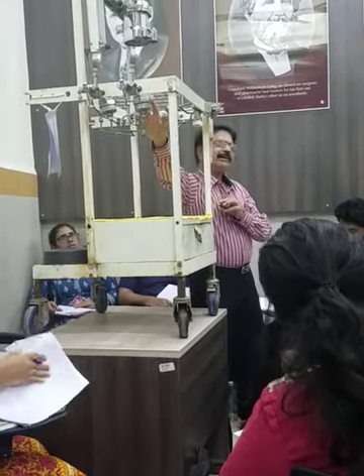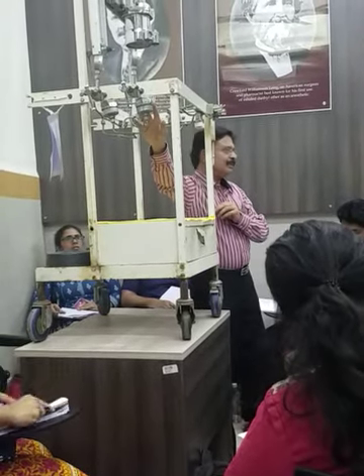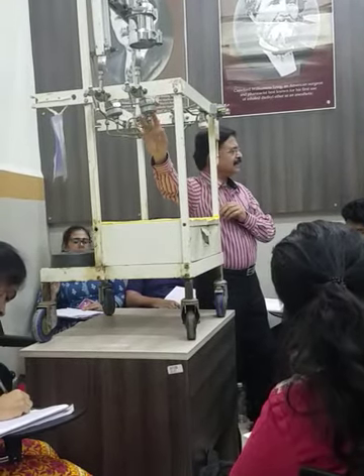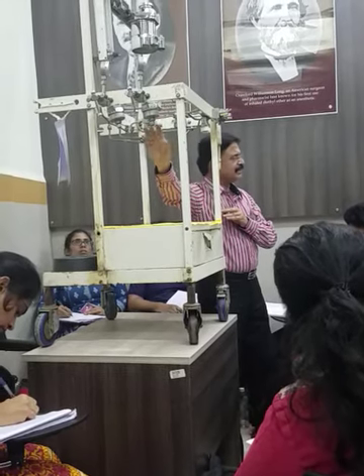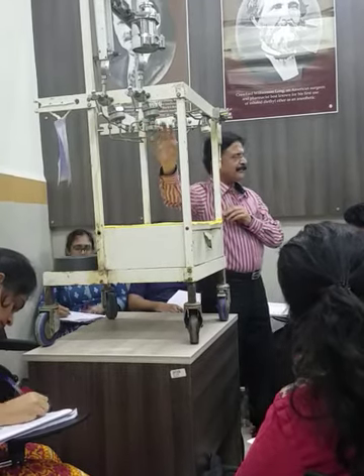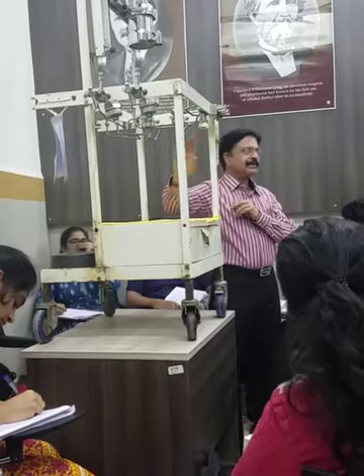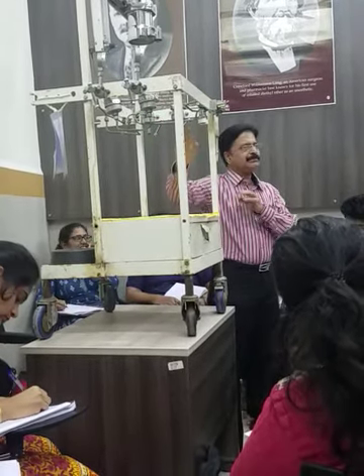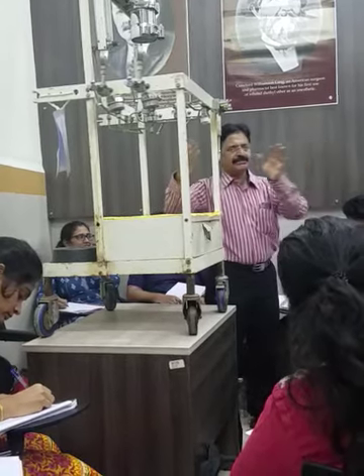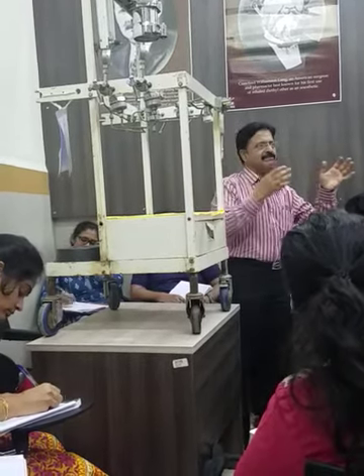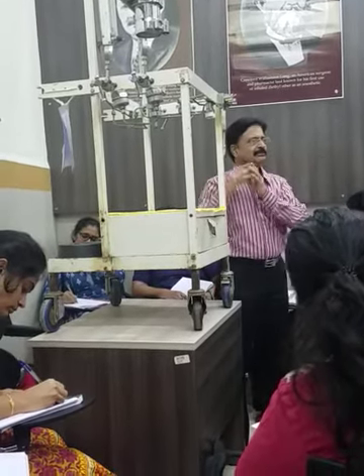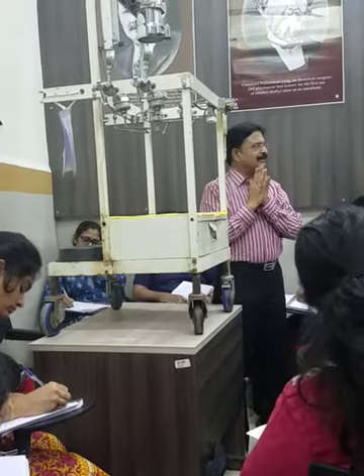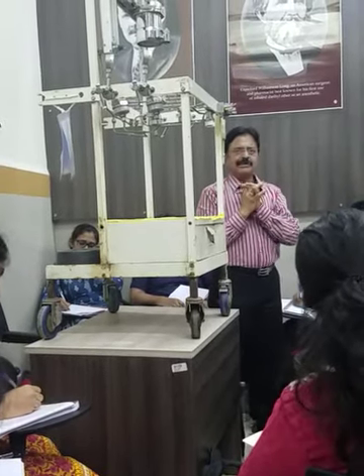Downstream of the pressure regulator is the intermediate system. You should know what is upstream and downstream. Downstream is always towards the patient — whatever is going towards the patient is downstream. Whatever is away from the patient is upstream.